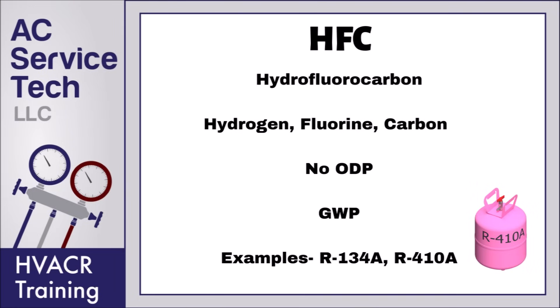HFC refrigerants were developed to be used instead of refrigerants that had chlorine in them. Since it doesn't have chlorine, it has no ozone depletion potential. Hydrofluorocarbon is made up of hydrogen, fluorine, and carbon. It has no ODP but does have a global warming potential, in some cases a very high global warming potential. Some well-known examples are R134a, used in automobiles and refrigeration, and R410A, used in residential and commercial air conditioning systems.